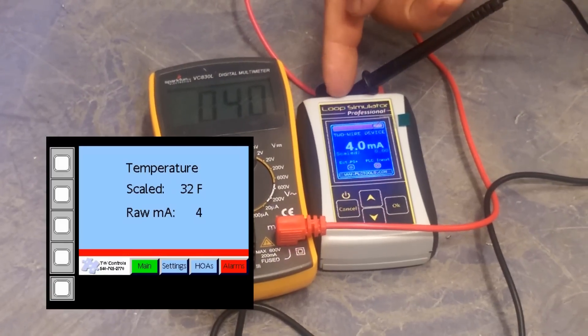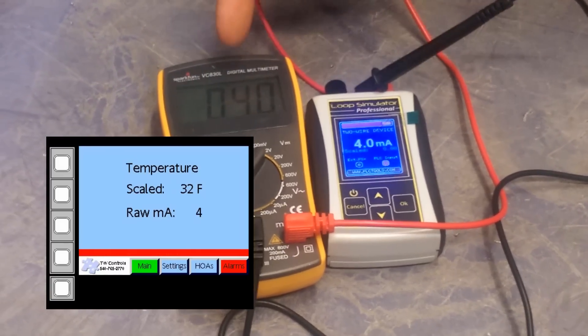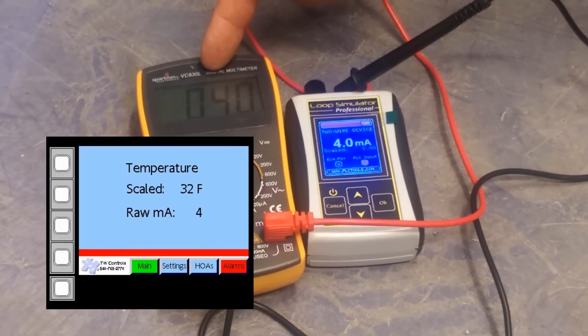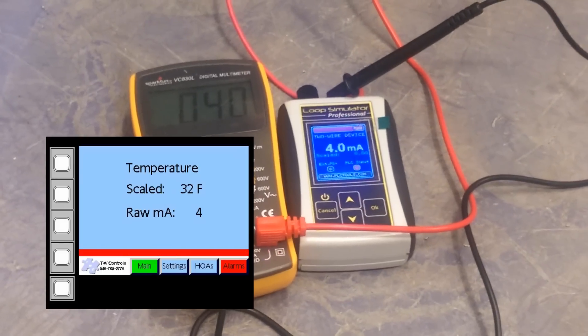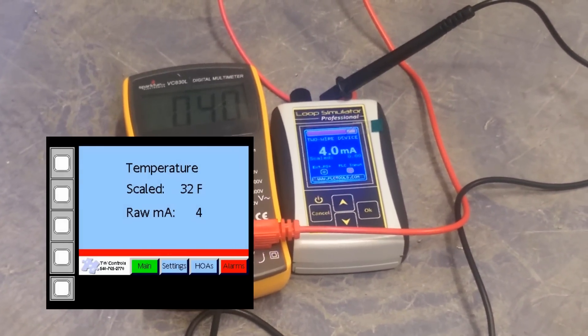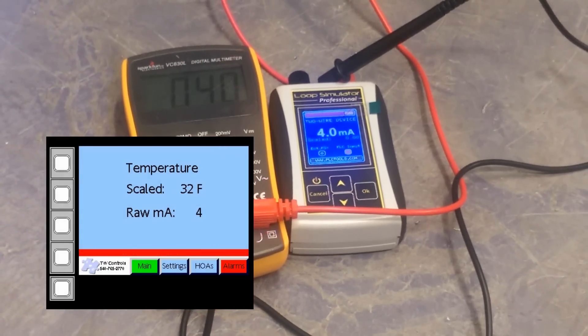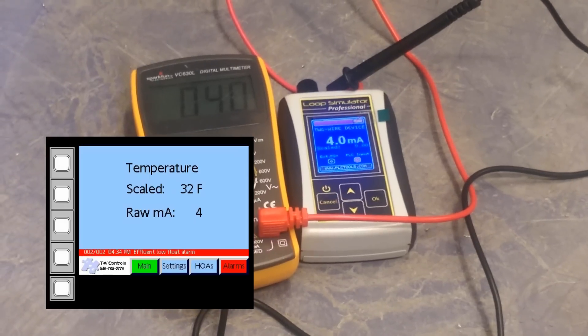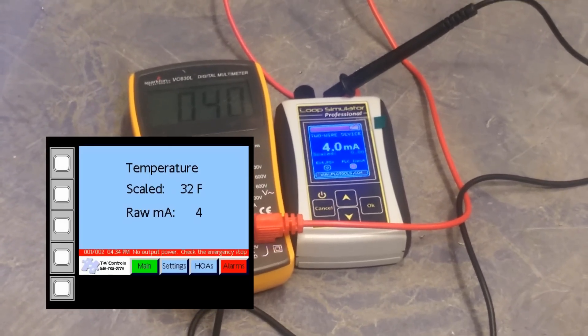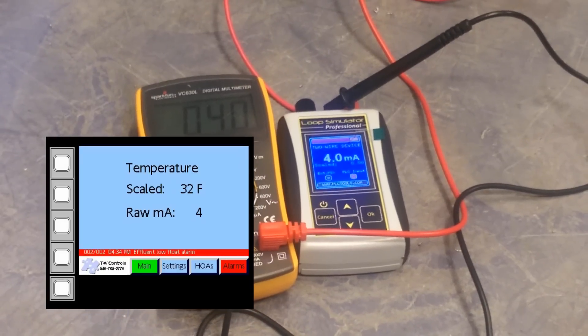As you can see, we have a four milliamp signal coming out of our simulator. Our meter is showing a four milliamp signal. And our HMI is showing a raw milliamp of four. And since we are simulating a temperature probe here, which has a scale of 32 to 140, it is showing 32 degrees.